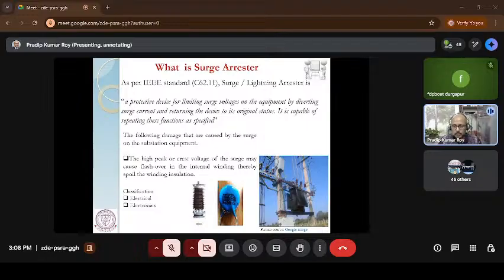In the electrical sector, the rating of a surge arrestor is a little bit high. It's mostly in the kV range. But if I talk about electronics, it is mostly in the voltage range, I mean some volts or some millivolts. So that is the only difference.